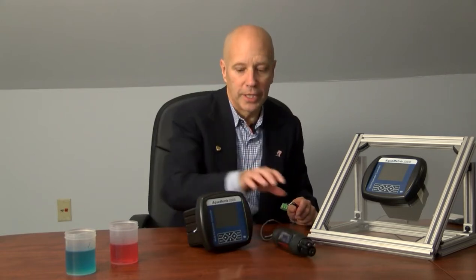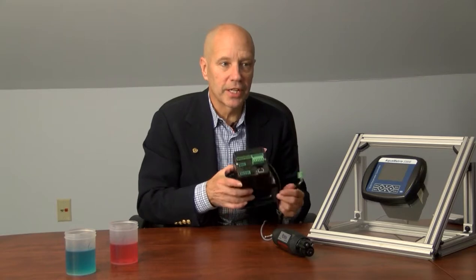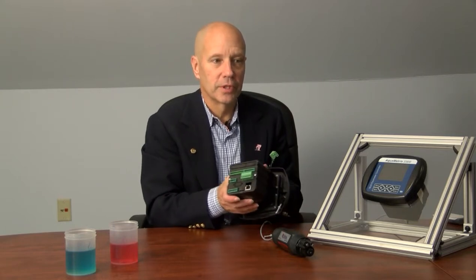First, let's connect the power cord, attach an Ethernet cable, and connect the sensor. We're using an AquaMetrix P65C8, a 2-wire direct output version of our differential pH sensor. All connections are on the back of the unit. The connector block in the middle of the right of the block can connect 4 4-20 milliamp analog sensors. There are 2 terminals that supply 24 volts, 1 terminal that supplies a ground, and 4 terminals for the 4 sensors. Some 4-20 milliamp sensors are loop powered, which means that they obtain their power from the loop itself.